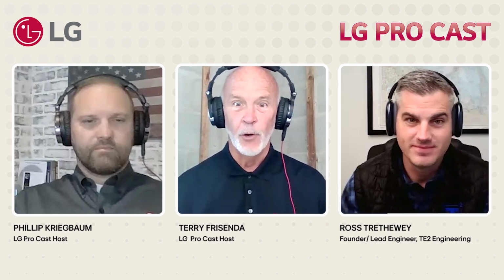Right. So that's really, I mean, when you talk about runtime, even with the DX system, we're out trying to challenge contractors to get these things sized correctly so that they run longer, especially with our inverter driven compressors. When they're running longer, they're performing better. They're using less energy overall than they are stopping and starting. So it's interesting that air to water does the exact same strategy. That's right. Yeah, you think about it, right?